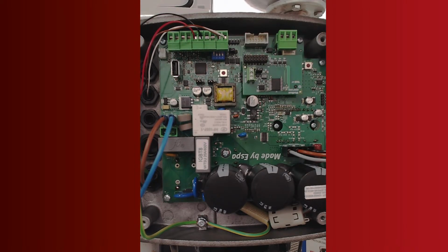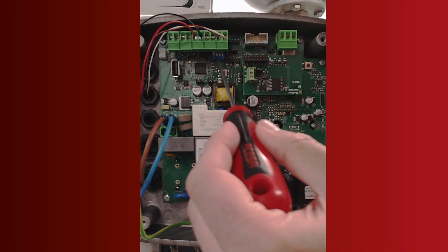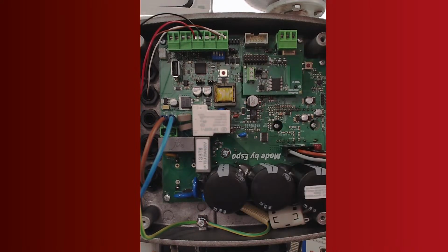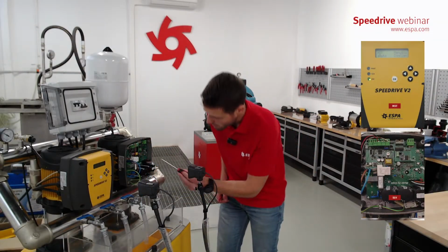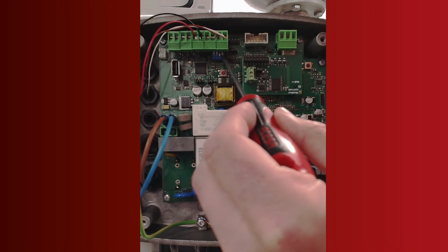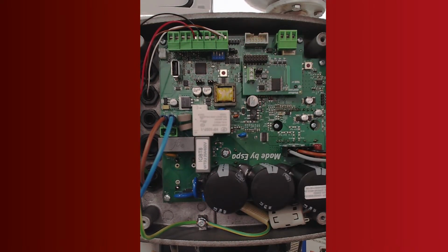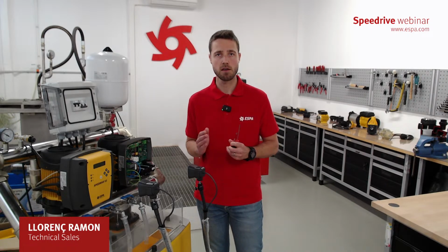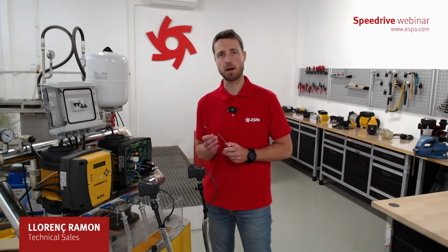The positions of the micro switch are all covered in the different manuals that we will send to you. There is a compatibility manual. So we will leave it at 2. If I open number 1 and number 2, for example, it will indicate that it's slave number 3. And if I move micro switch number 4, it indicates that we are working with a Speedrive from the old ones. So the new Speedrives, the yellow ones, communicate perfectly with the old ones as long as we configure micro switch number 4 correctly. We will leave it back as before. Okay, sorry.